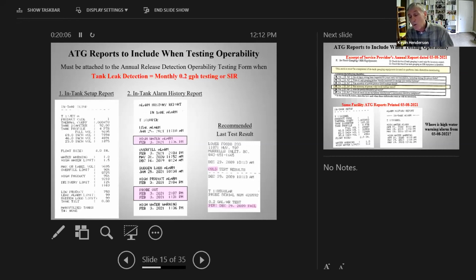And of course, I always like to do this because if I'm pulling the tank gauge and probe, typically it's because someone is doing 0.2 testing, whether that's static or CSLD, or maybe it's an in-tank SCALD. I am just going to print the last passing 0.2 test in that system. I'm also going to make that part of the report, because clearly the reason that we're pulling the probe is because they are doing 0.2 testing. You want to make sure that it is in fact doing 0.2 testing. So the easiest way for me to do that is to simply print the last passing or last test result for 0.2.